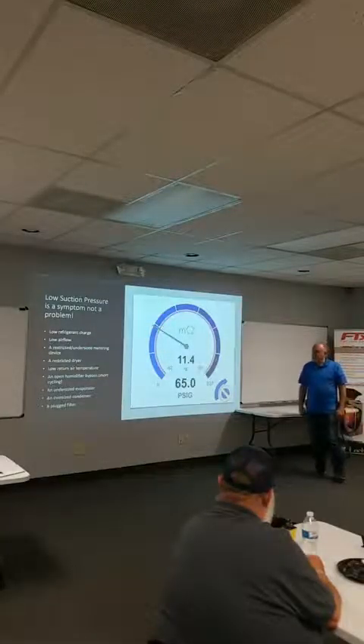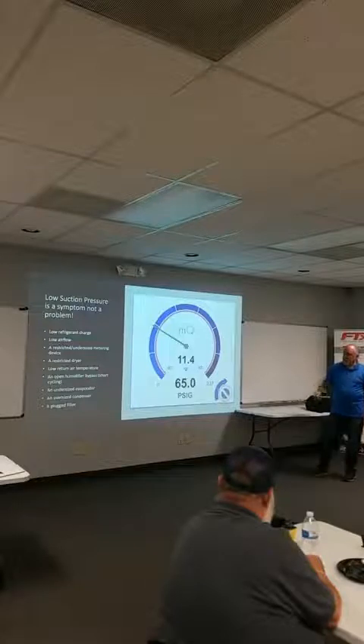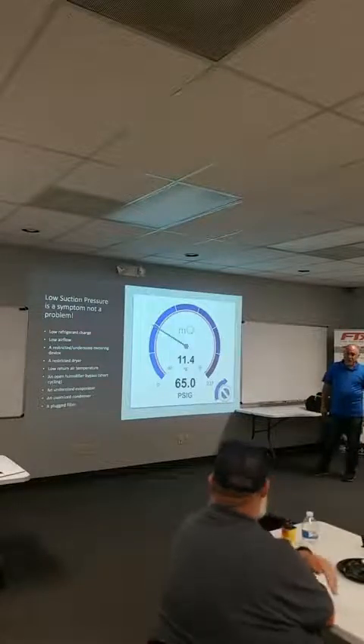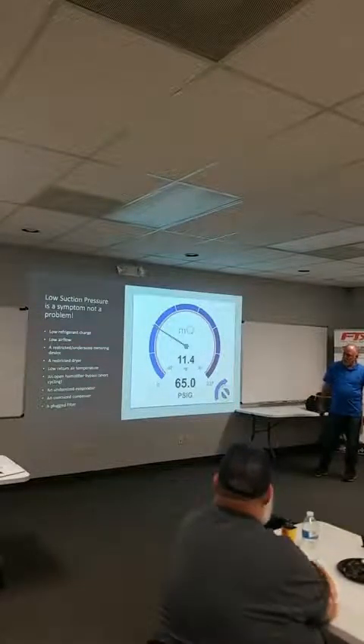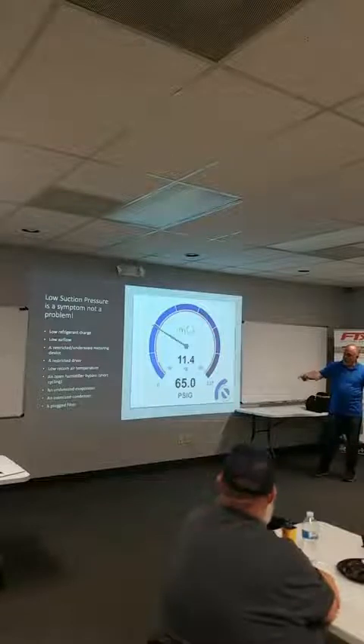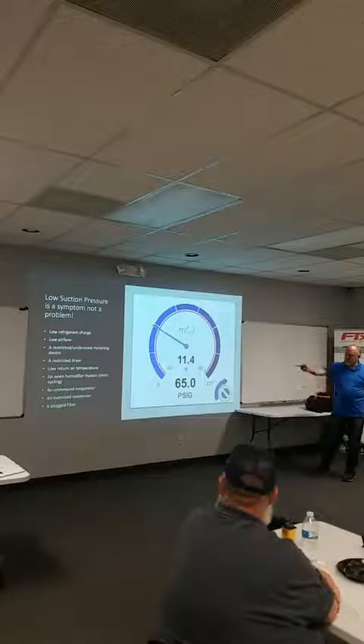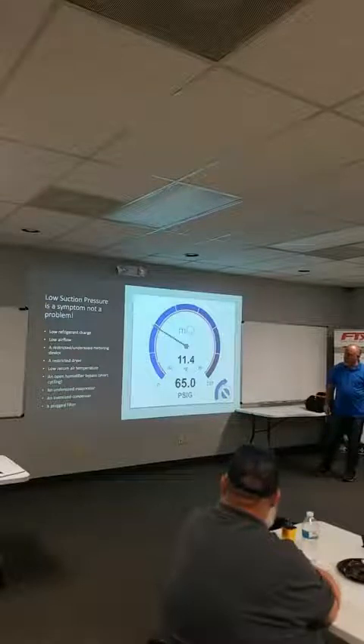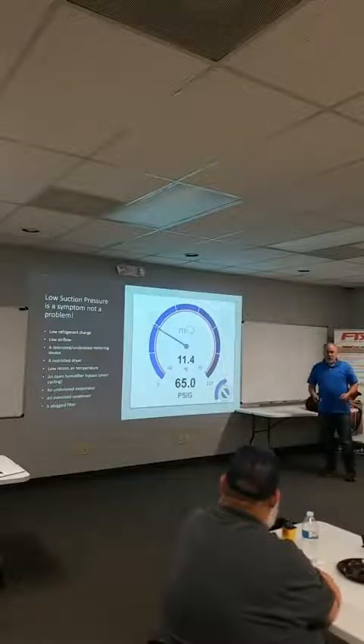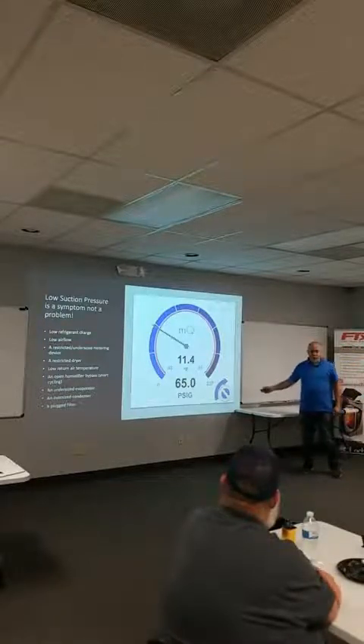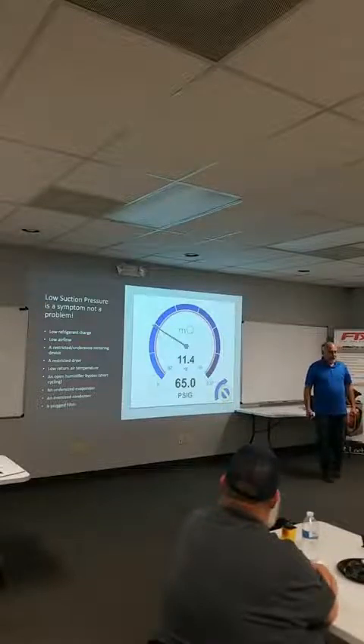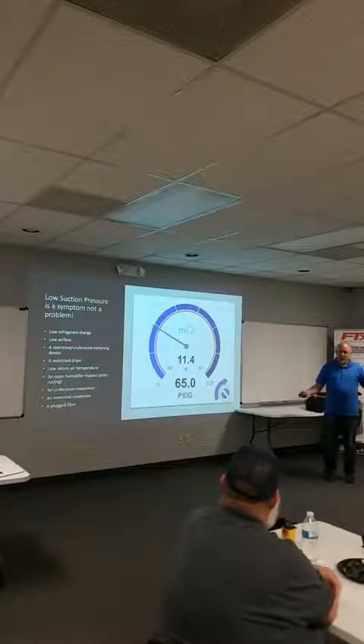Here's an example, right? Low suction pressure. That's a symptom, it's not a problem. Everybody says, oh, the problem's low suction pressure. No, it's probably low refrigerant charge, or it could be low airflow, restricted metering device, or restricted dryer, or low return air temperature, right? Humidifier bypass open, undersized evaporator, oversized condenser, plugged filter, right? But nobody's gonna say, oh, suction pressure's low, let me turn up the suction pressure adjustment screw and get that where it belongs, right? We can't just turn that stuff up.